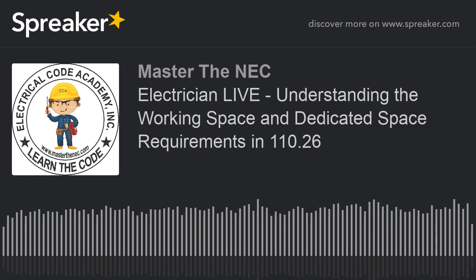Well, I guess we're going to finish this up because I wasn't going to do it, but we're so close. Let's just do F and end this thing. F is dealing with locked electrical equipment rooms or enclosures. It says, electrical equipment rooms or enclosures housing electrical apparatus that are controlled by locks shall be considered accessible to qualified persons. Okay, so it's basically a statement that says, even if it's behind a lock of some type, maybe an electrical equipment room or a large piece of a large enclosure, it could have a lock on it. Okay, it's still considered accessible. All right, to get to the equipment. All right, by who? Qualified persons.